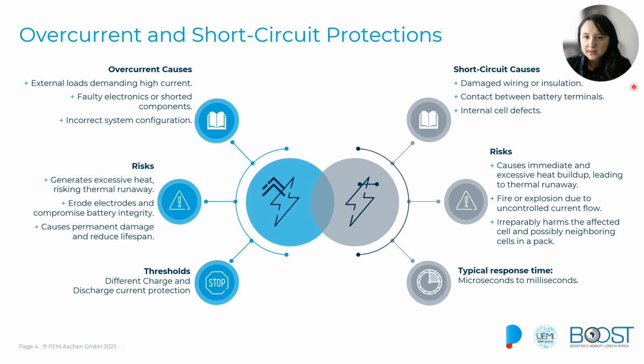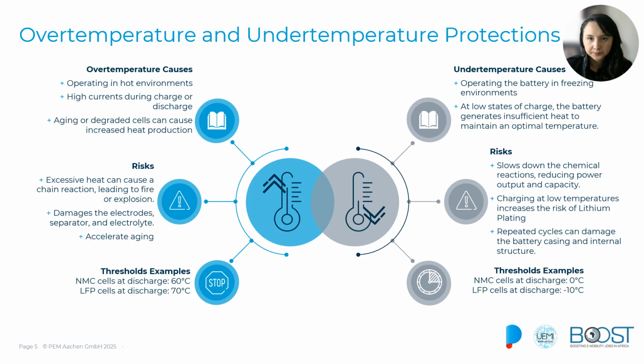Short circuits result in massive and uncontrolled current flow that generates a lot of heat, and this will cause immediate damage and affect the cells, potentially even initiating a thermal runaway event. To protect against this, the BMS is designed to react very quickly, in milliseconds or even microseconds, to disconnect the battery and to prevent further damage and escalation of the damage when a short circuit is detected.